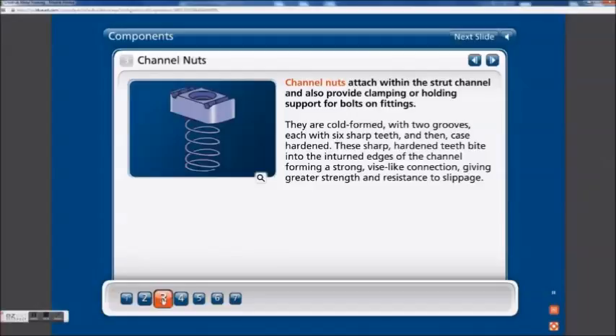Channel nuts attach within the strut channel and also provide clamping or holding support for bolts on fittings. They are cold formed with 2 grooves, each with 6 sharp teeth, and then case hardened. These sharp, hardened teeth bite into the inturned edges of the channel, forming a strong, vise-like connection, giving greater strength and resistance to slippage.